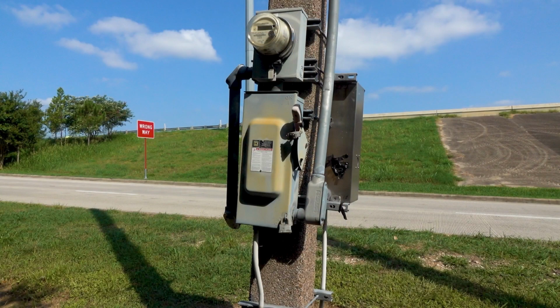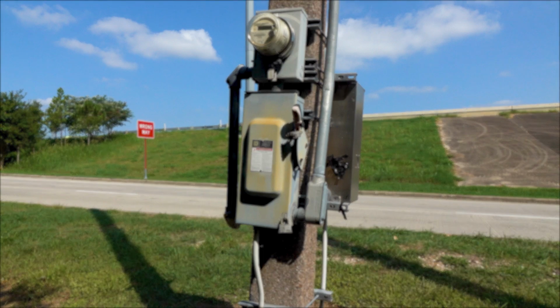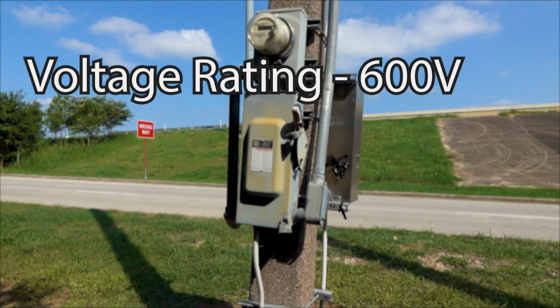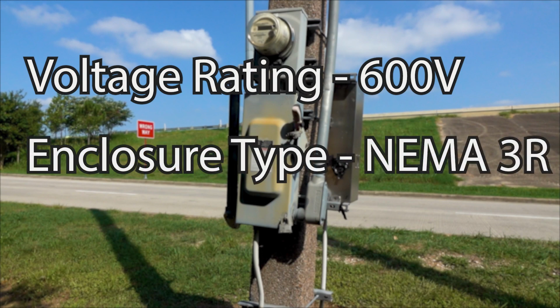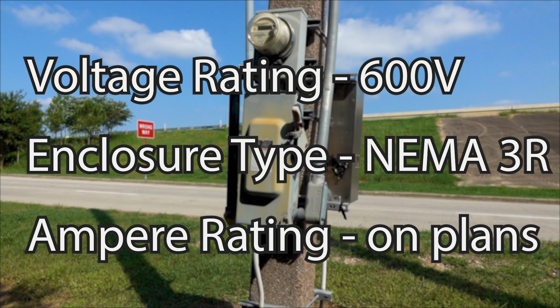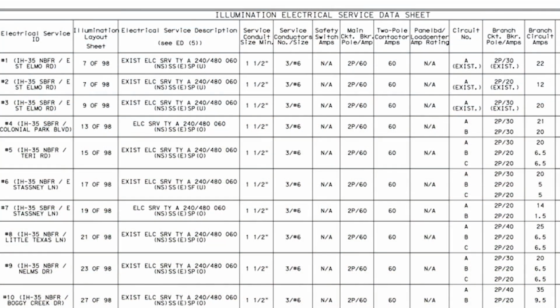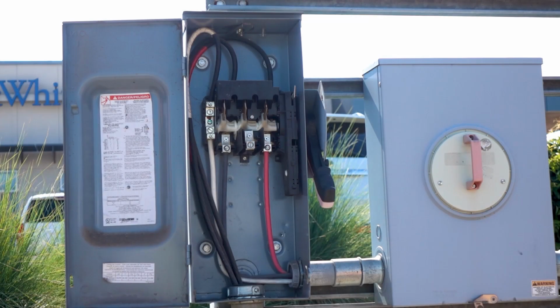3 ratings must be confirmed during the inspection of this switch: the voltage rating, 600 volts, the type of enclosure, NEMA 3R, and the ampere rating located in the plans on the electrical service data chart. The inspector should compare the electrical service data chart in the plans to what has been installed on the project. Since this switch is installed on the utility company side of the meter, the serving utility will typically place their own padlock on the switch before power is applied to the service.